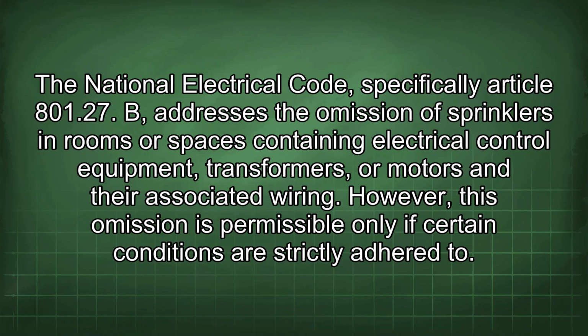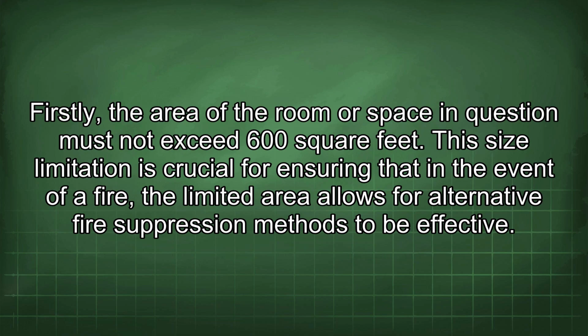The National Electrical Code, specifically Article 801.27b, addresses the omission of sprinklers in rooms or spaces containing electrical control equipment, transformers, or motors and their associated wiring. However, this omission is permissible only if certain conditions are strictly adhered to. Firstly, the area of the room or space in question must not exceed 600 square feet. This size limitation is crucial for ensuring that in the event of a fire, the limited area allows for alternative fire suppression methods to be effective.